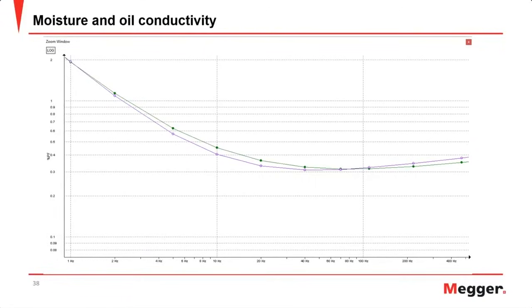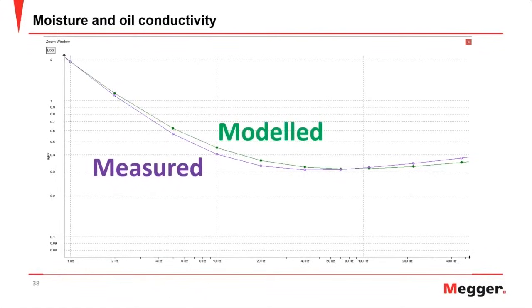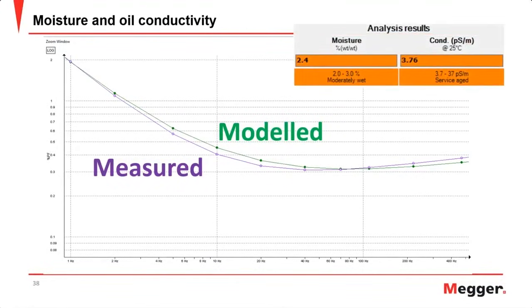And dielectric frequency response is looking at insulation from down to 0.1 millihertz up to 1000 hertz. And when we do that, we can take our measured power factor plot and we can compare that to a model. And for a bushing, that model is going to be how the oil and the paper inside relate to one another. They call this the XY geometry. And if we know that approximate geometry, we can compare that to our measured values. And when we do that, we can determine the moisture that is within the solid insulation, so the paper in bushings or the paper in the spacers and barriers within transformers. And then we can also determine the conductivity of the oil. So with this DFR method, we can truly understand the state of the bushing or whatever asset that we're testing.